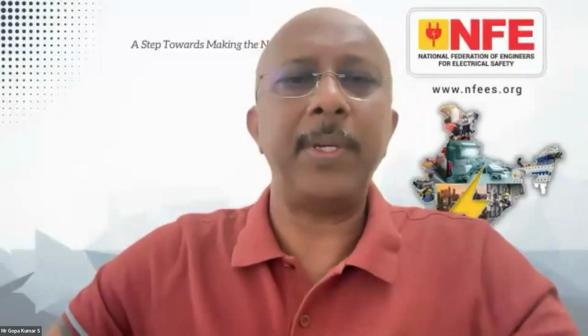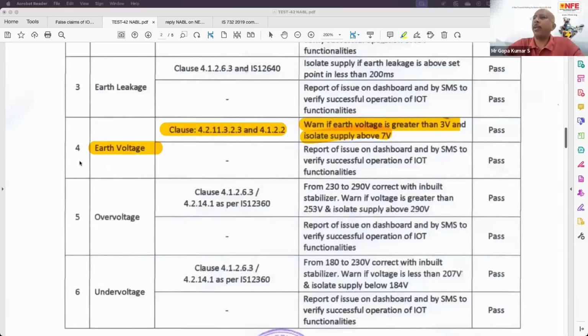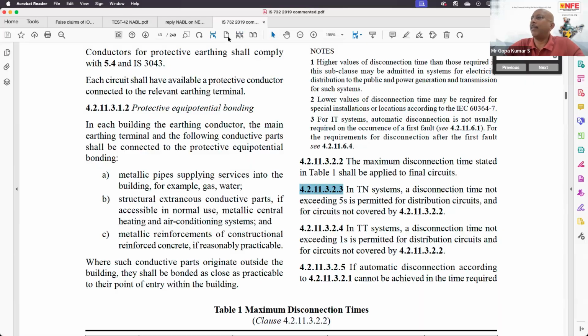Just for your information, I'm sharing the screen. You see in the test report, serial number 4, earth voltage, clause 4.2.11.3.2.3 and 4.1.2.2 of IS 732. Now let me take IS 732, clause number 4.2.11.3.2.3.